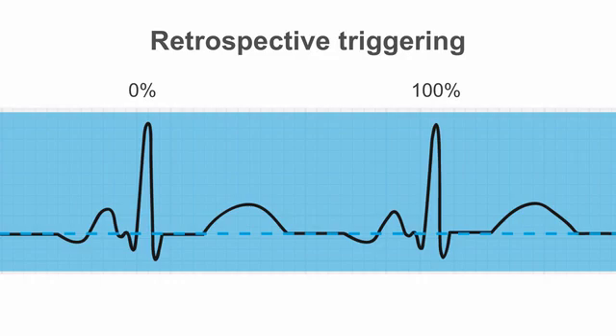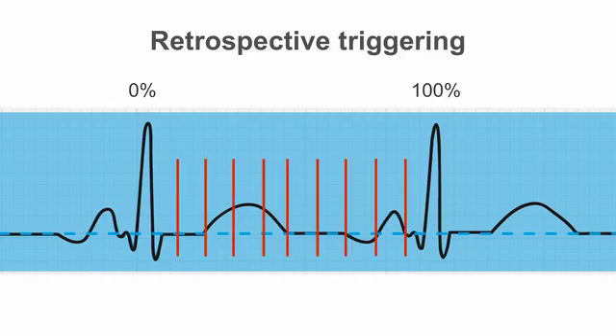When we take two consecutive R-waves, this is known as the R-to-R interval. The first R-wave represents 0% of the R-to-R interval and the second R-wave 100% of the R-to-R interval. To obtain moving pictures throughout the cardiac cycle, the X-ray tube must be on for the duration of the cardiac cycle — in other words, 100% of the R-to-R interval. Normally, images are reconstructed at every 10% phase to obtain a moving image.